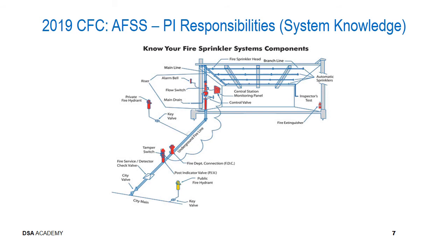Here's a detail of an underground fire line showing the location of the fire department connection, post indicator valve, the supply to the sprinkler system, and note that this underground fire line also supplies an on-site private hydrant. The basic components of the sprinkler system are going to include the riser, the supply piping to the branch lines, and the branch lines to which the sprinklers are connected.